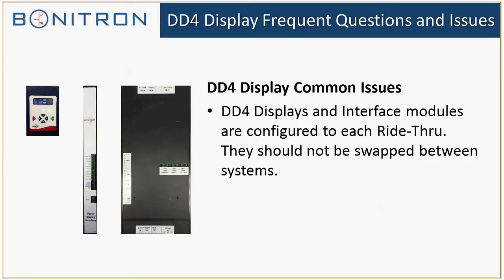That way we can understand the current and the voltage ratings, and they're calibrated just to read those. If you just swap those around, these calibration points change, and while it is possible to readjust this in the field, it's not easy, and we really strongly advise against changing the displays around. So we really do like pairing each interface module, display, and ride-through system if we can. We can go back and redo it. It just provides a challenge, especially doing it over the phone. By and large, it's almost quicker just to send it back to us if the boards have been swapped around, or if there's been changes made, and we can go and redo the calibrations here at Bonitron.